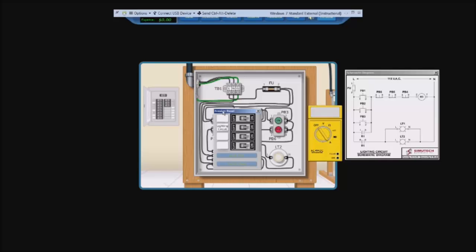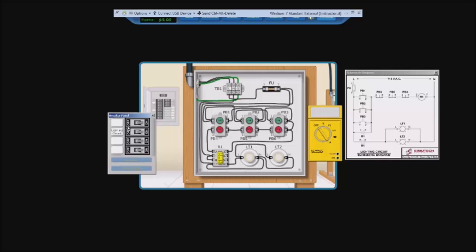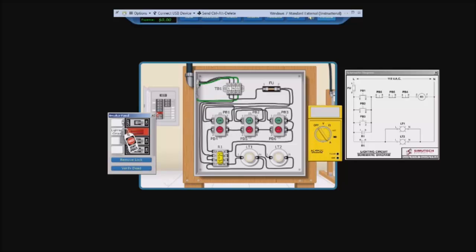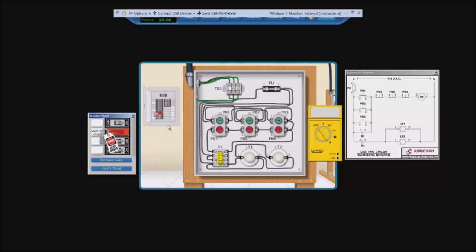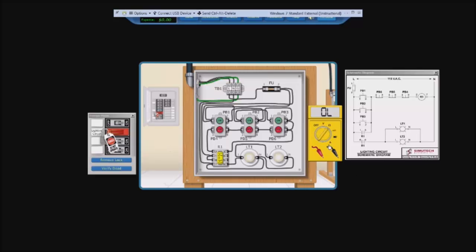So let us open up our breaker panel, turn off our power, lock out and verify dead. You must make sure you verify it is dead. Because if you try going to put stuff on there, it will ding you for it. And if you don't turn off your power and then you go disconnecting stuff or putting a meter set to ohms on here, it will basically fail you on your assignment.